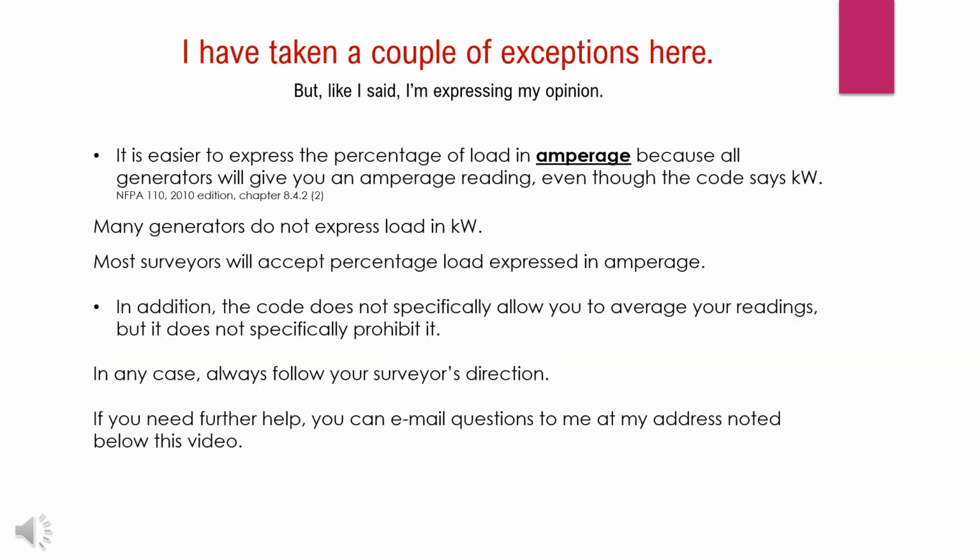I have taken a couple of exceptions here, but like I said, I'm expressing my opinion. The first is, it is easier to express the percentage of load in amperage because all generators will give you an amperage reading, even though the code says kW. Many generators do not express load in kW. Most surveyors will accept percentage load expressed in amperage.